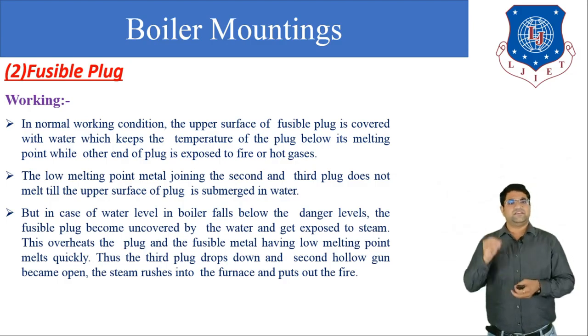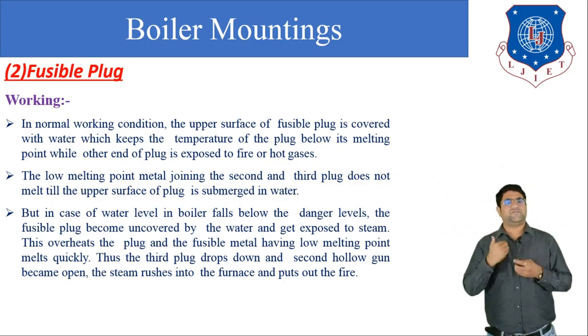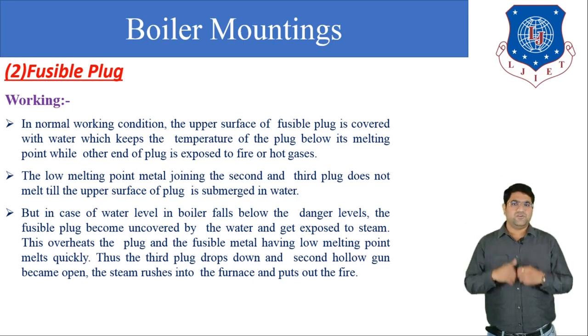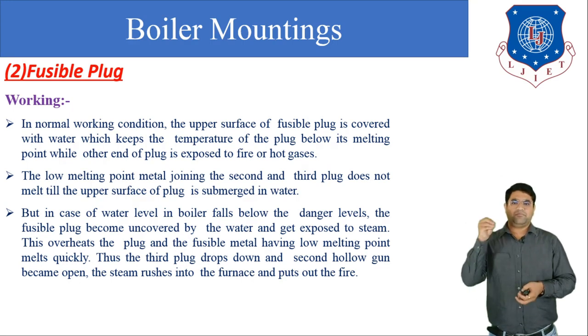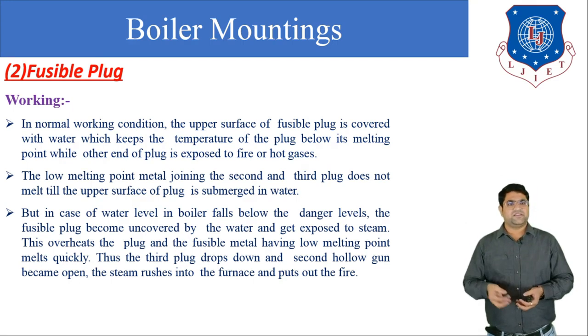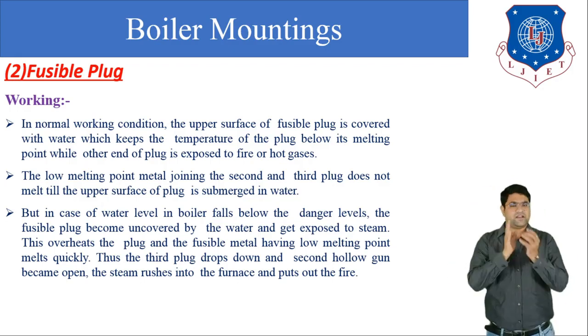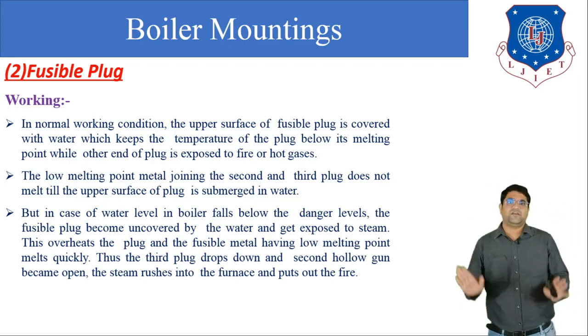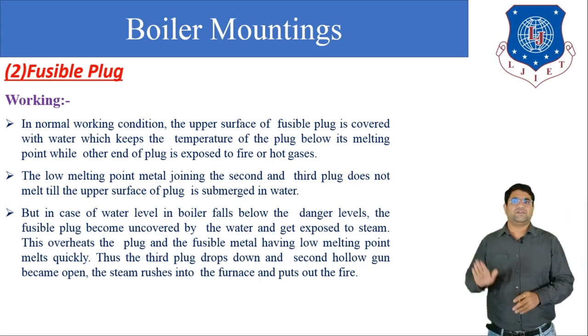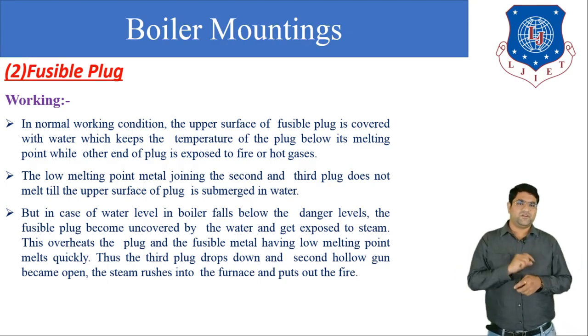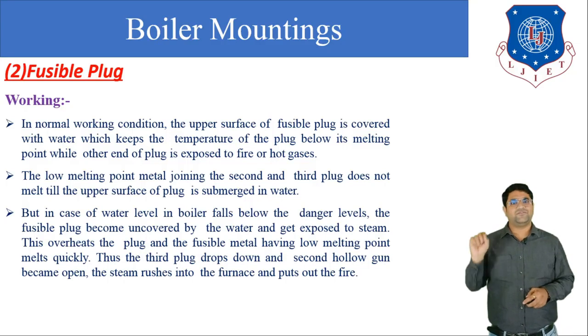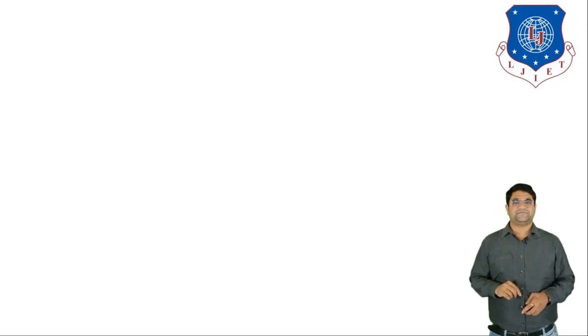So we can say that this overheats the plug and the fusible metal, having a low melting point, melts quickly. So the third plug drops down and the second hollow gun metal plug will open. The steam will rush into the furnace and, after all, it will stop the furnace. So we can reduce the overheating with the help of this fusible plug. Okay, so this is all about the working of the fusible plug.